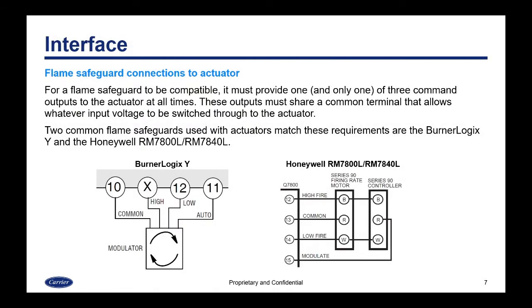So, the connections from the flame safeguard to the actuator. For a flame safeguard to be compatible, it must provide one and only one of 3 command outputs to the actuator at all times. These outputs must share a common terminal that allows whatever input voltage to be switched through to the actuator.